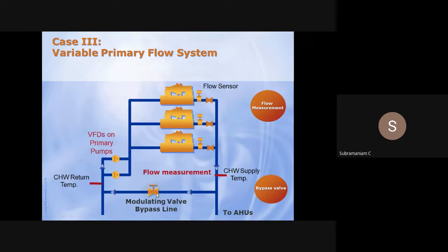And in the decoupler line, you will see a modulating bypass valve. So this is a topic we can take as one separate day if you want. We can take half an hour to 45 minutes on how exactly this variable primary flow and this primary secondary system works. Maybe we can have one separate session on that if you want.